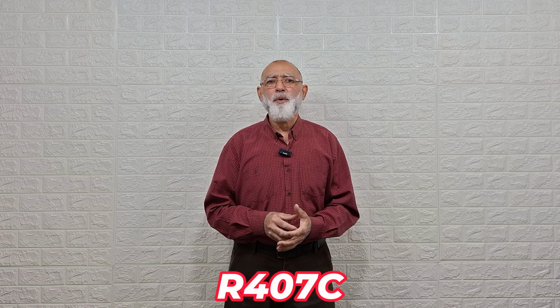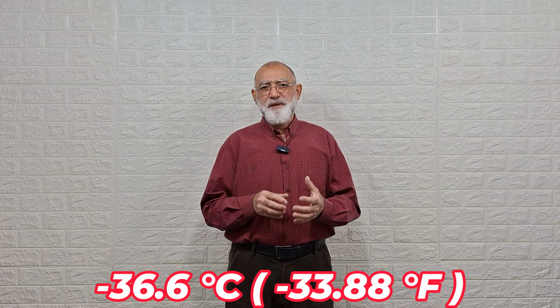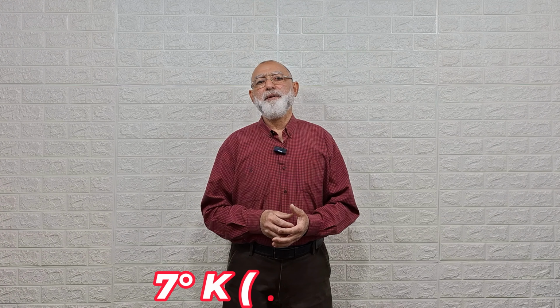R407C freon starts boiling at minus 43 degrees Celsius at normal atmospheric pressure, but the process ends at minus 36.6 degrees Celsius. That is, the temperature glide of the freon is 7 Kelvin.